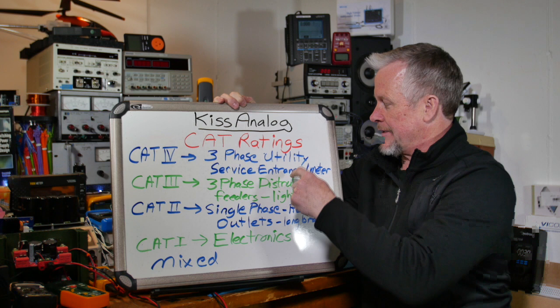Okay, guys, so the CAT ratings. This is surge. You can have a surge in Cat 4 up to 8,000 volts. And that source of the surge might only have 2 ohms. So that's 4,000 amps. So yeah, the MOV has got to be big enough to handle that.